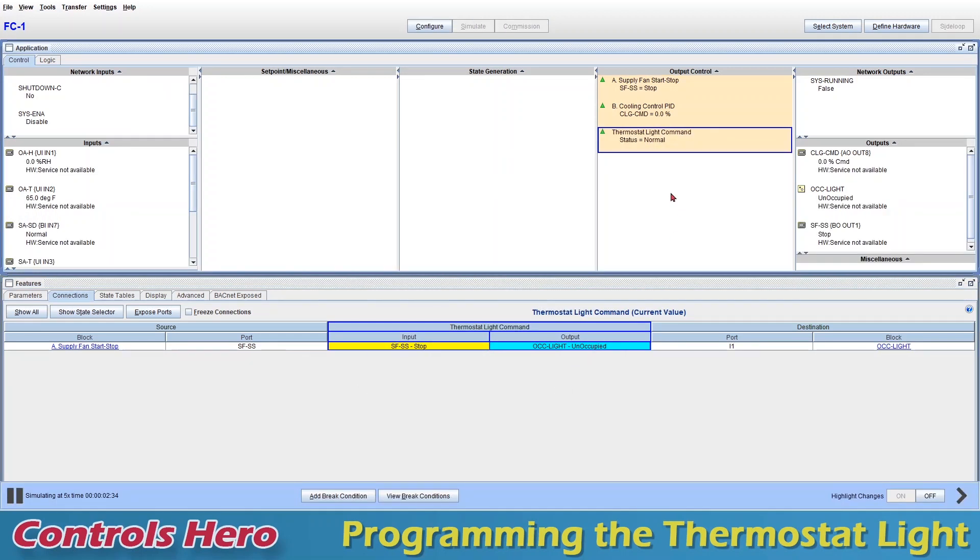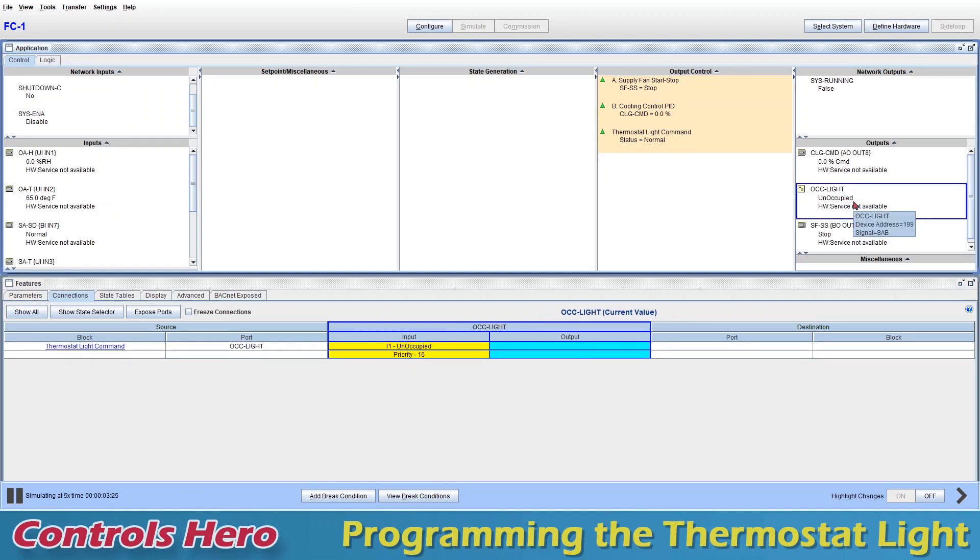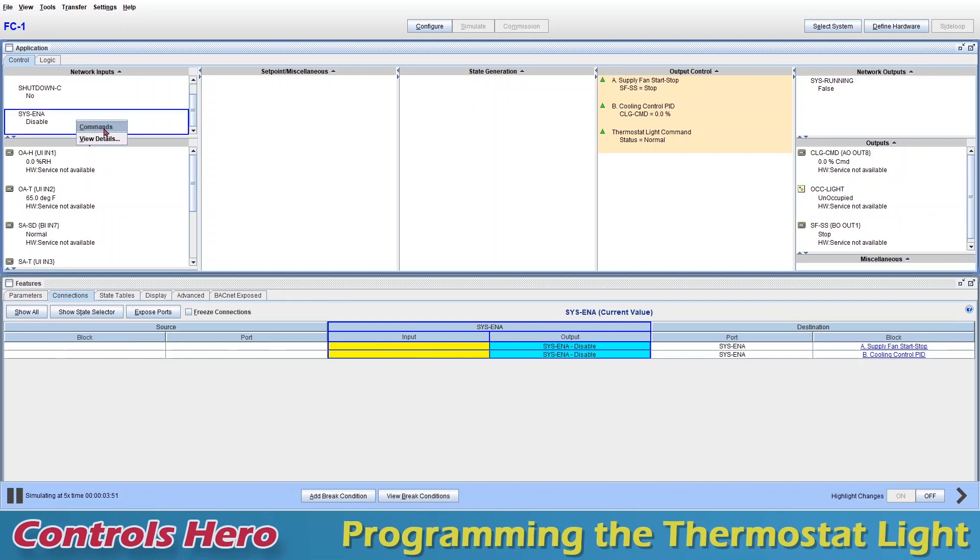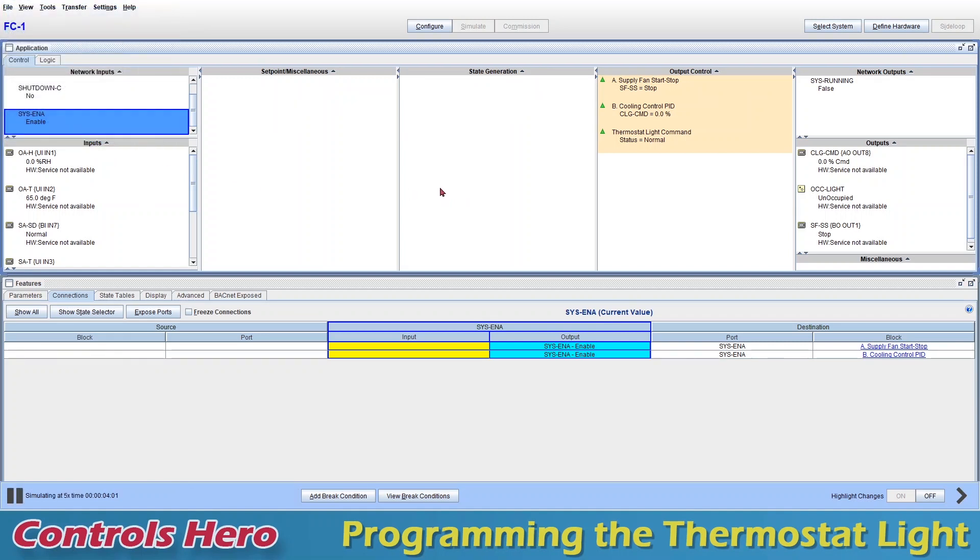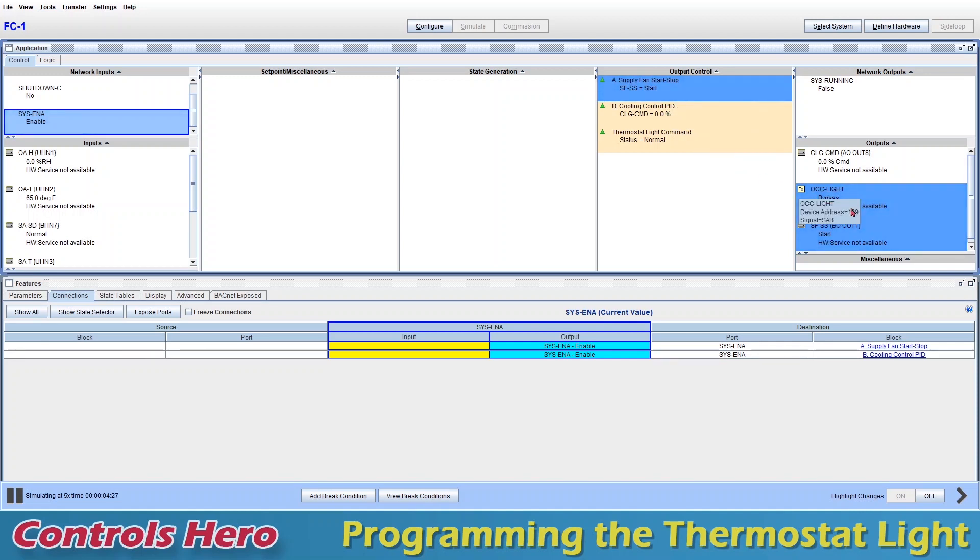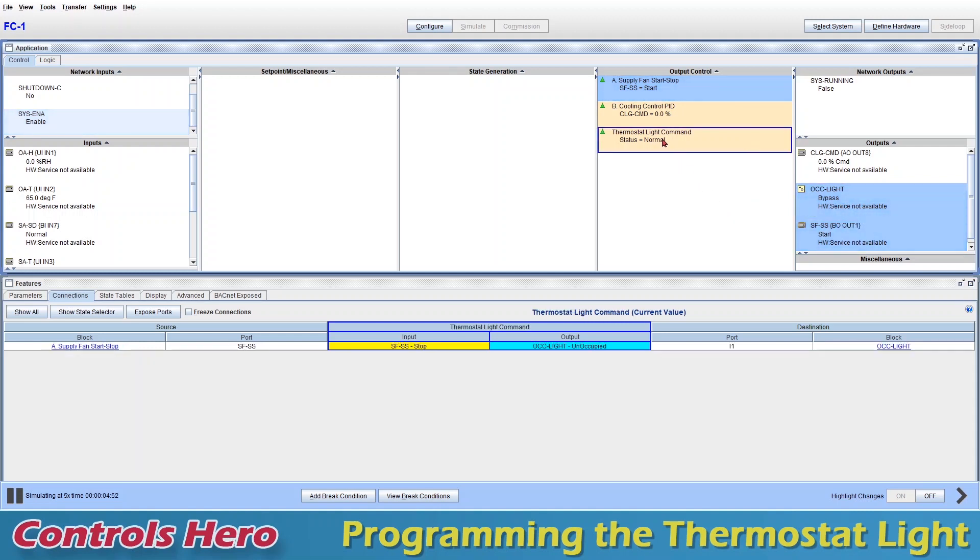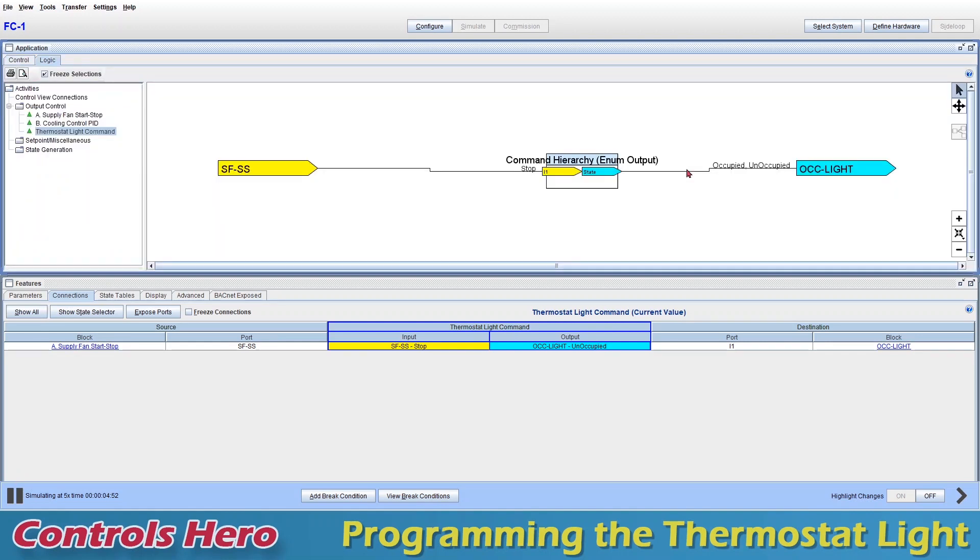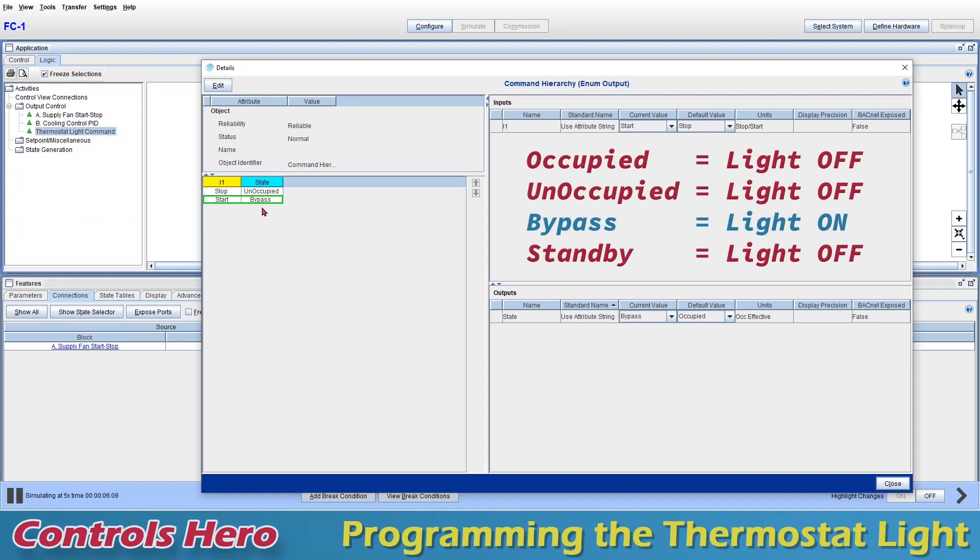Okay, so I just started a quick simulation to show you how this works. Basically, we have my fan stop, that means that my occupancy light is commanded to unoccupied, so it will be off. Let's start the fan by enabling the system enable. I'm going to click Enable, OK, Send. The fan should start anytime soon. Start, and you can see that the occupancy light was commanded to bypass, so bypass means light on. If I right click into my module, we can see that the logic is working, and if I go inside, you can see the actual state start equal bypass. Any other value other than bypass is not going to work, the light is going to be off, even occupied. So occupied, unoccupied, or standby, the light will be off. So bypass is the only value that works.